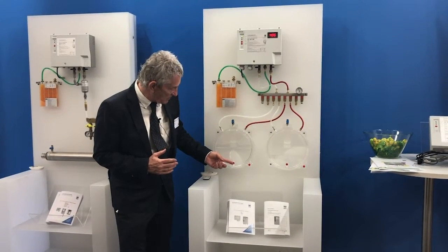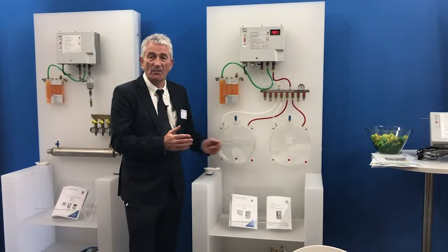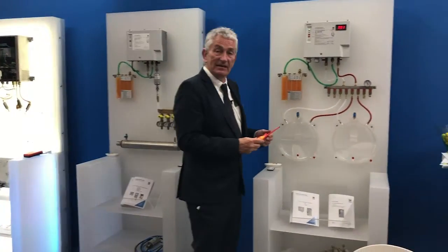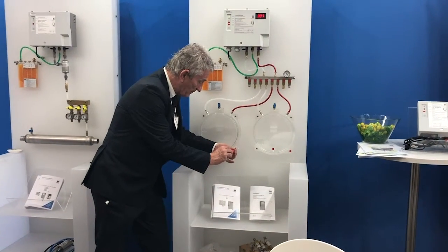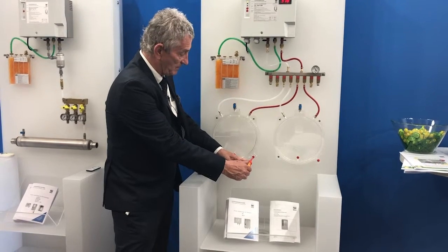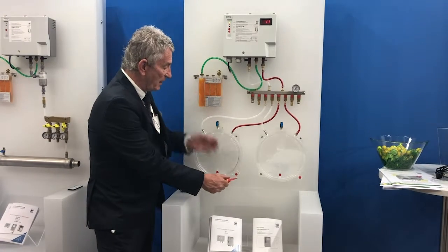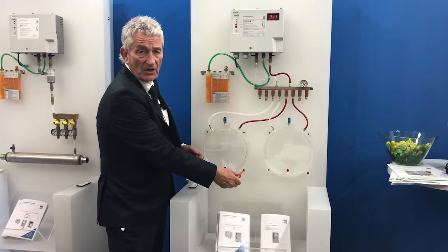It's an interesting situation when you see exactly what happens when some air gets into the interstitial space. And with the help of my assistant, Jos Berg, owner of the company — thank you, Jos. You can see what happens. This simulates air coming in from the outside into the interstitial space. Even I can hear that. That's the alarm that goes off whenever that happens.